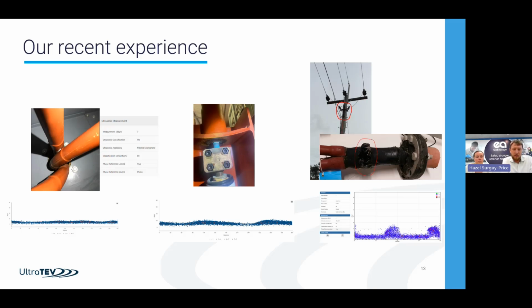The final one is a cable crutch which was producing TEV activity on the earth, but also strong ultrasonic activity - just demonstrating that you haven't got to be close to this discharge to pick it up. There are accessories that allow you to do this from a number of meters away at the base of the pole and identify the location of the discharge.